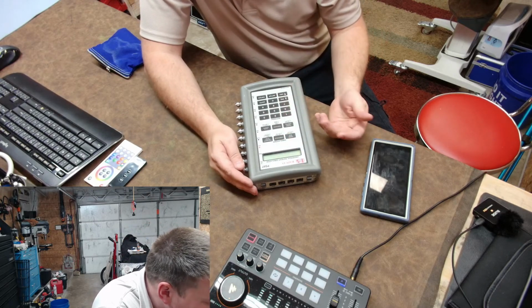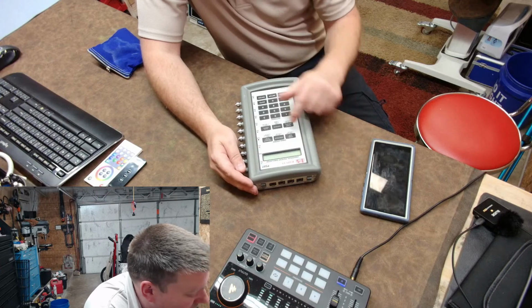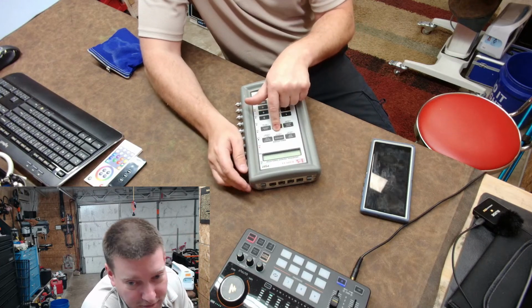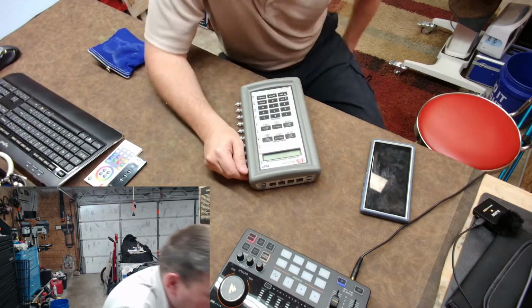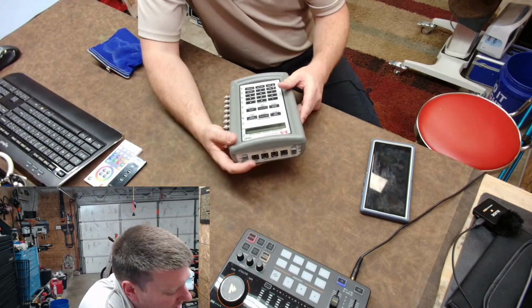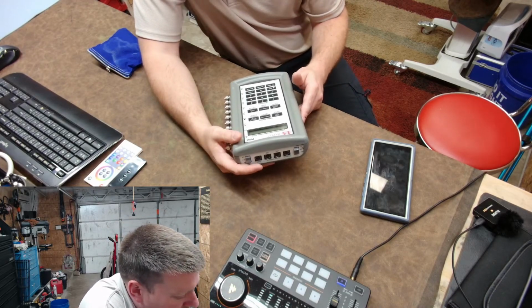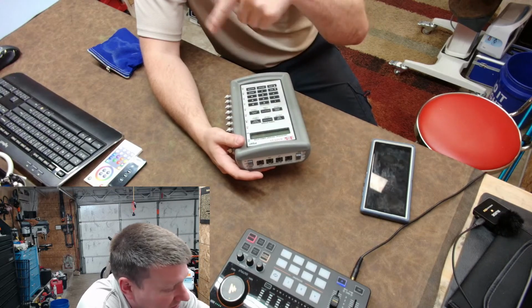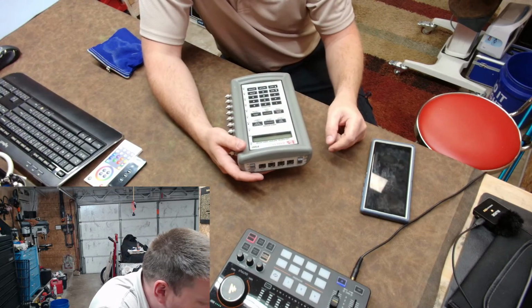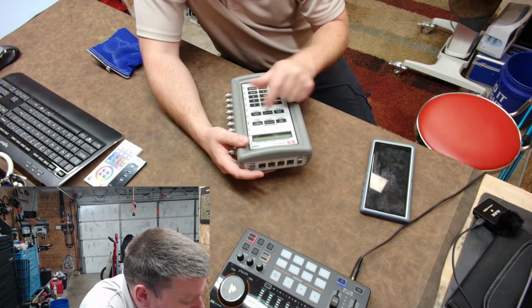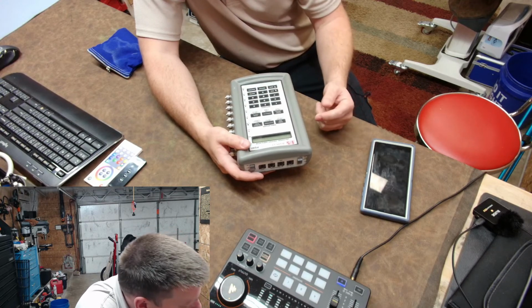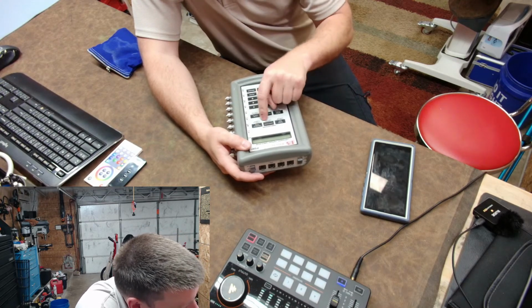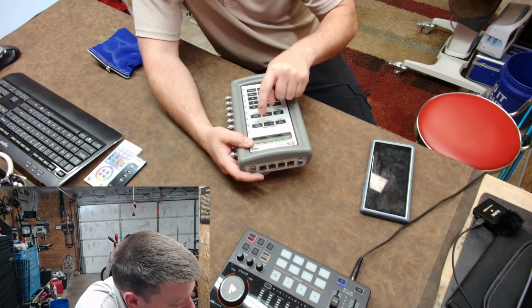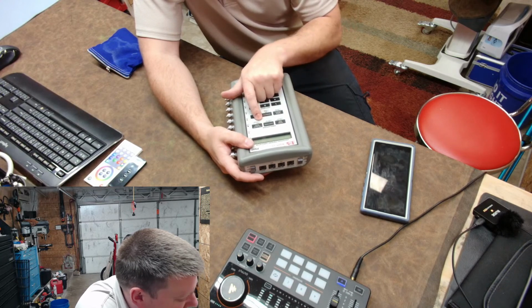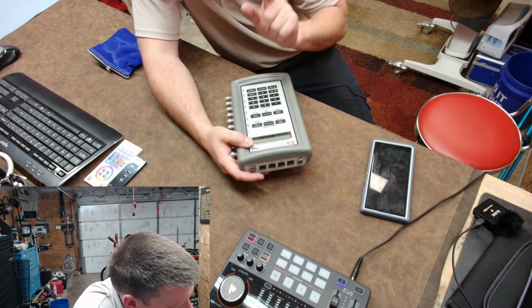Arrhythmias, so I can throw different arrhythmias up, or I can adjust the ECG millivolts, which is important because that all important 1 millivolt per division on the ECG trace. That's really important. I can do a sine, square, triangle, and pulse over here. And I can adjust the different waves. I can adjust the frequency and the ECG millivolts also on this one.